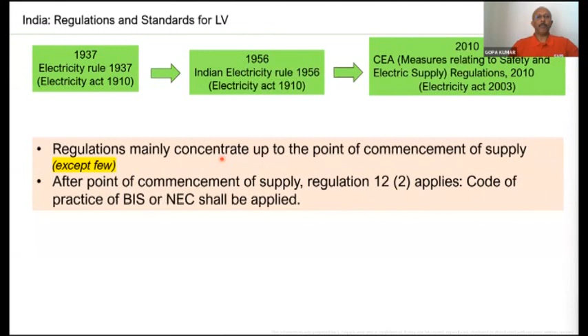Regulation 12.2 says for all other purposes, we are supposed to follow the code of practices made by the Bureau of Indian Standards or NEC. NEC means the National Electrical Code of India, not the NEC of America. So basically, within the building, we follow the code of practices or National Electrical Code, and outside, up to the meter board - easy way to say it is up to the meter board from the transformer - that is the responsibility of the electricity supply company.